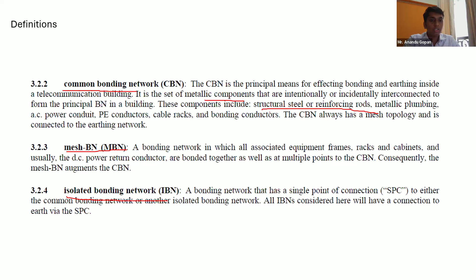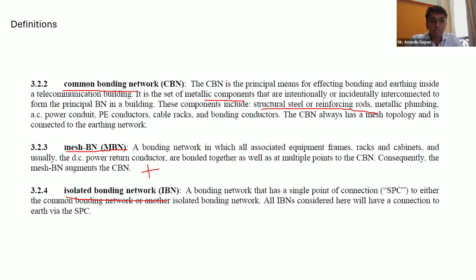Basically, you are connecting whatever dead metallic things you find in your building; you are interconnecting all of these dead metallic equipment, dead metallic parts. In the common bonding network, again, you will have interconnection for your telecommunication equipment. You will have a mesh bonding network and an isolated bonding network. This is isolated and this is the mesh bonding network. For the mesh bonding network, I'll just read the definition. It is a bonding network in which all associated equipment, frames, racks, cabinets, and usually the DC power return path, that is your positive, are bonded together at multiple points to the CBN, and they will form a mesh bonding network.